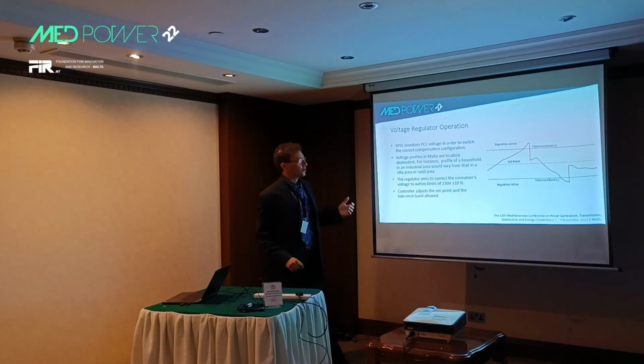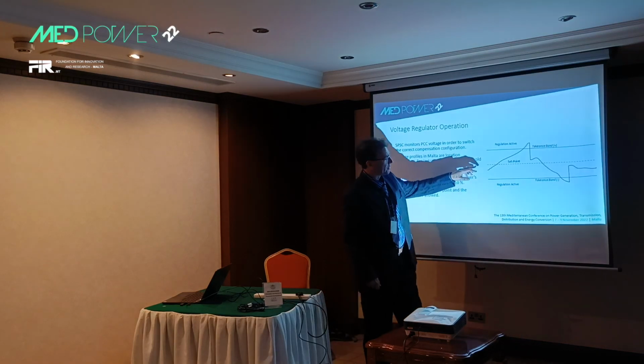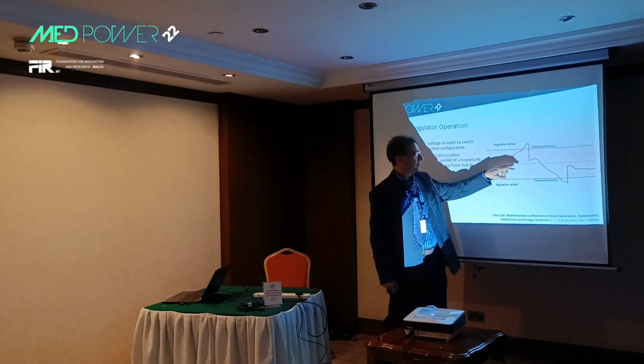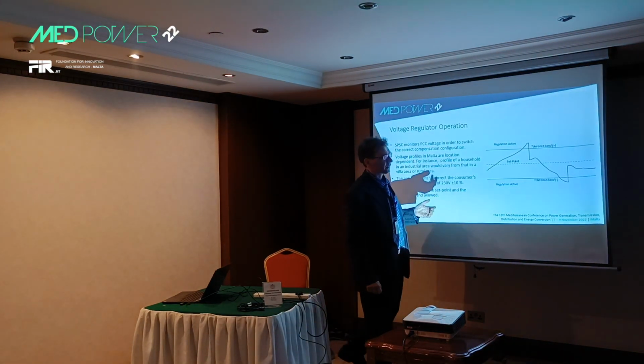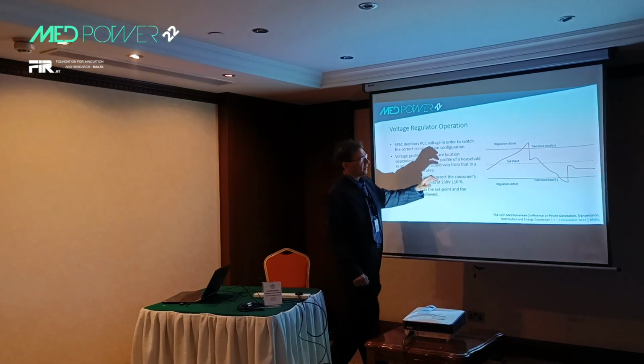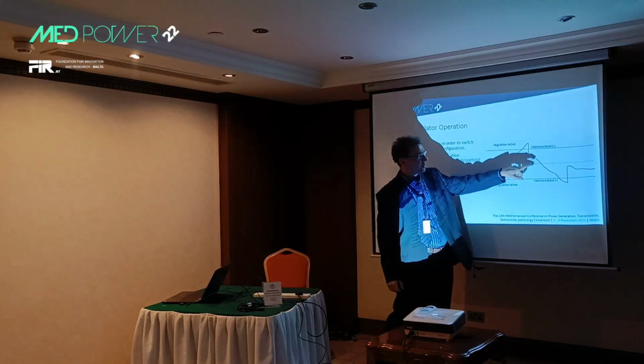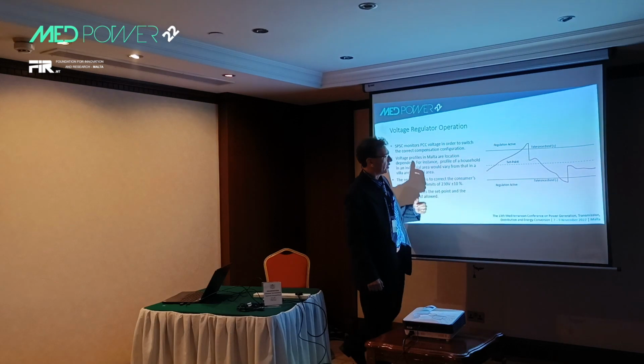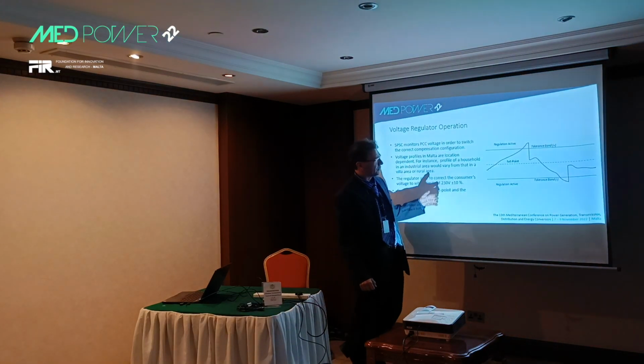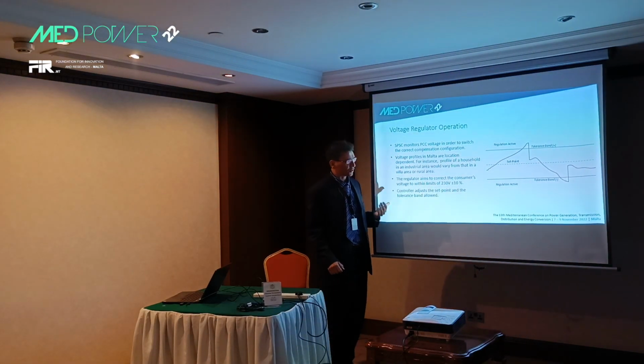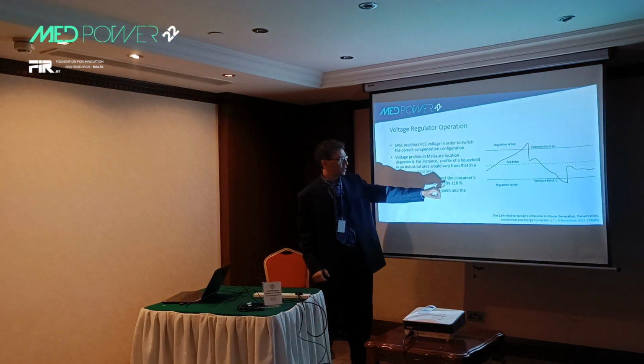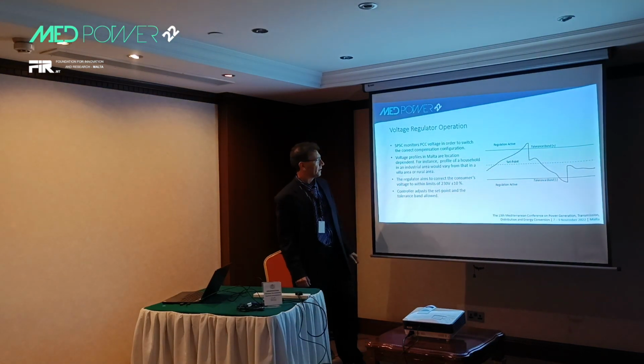How will the voltage regulator operate? Basically, a set point will be determined. That will be our 230 volts. And that tolerance band, that is when you are going to ask the controller to switch in. That is variable. The maximum correction that we are targeting towards is plus or minus 10%.